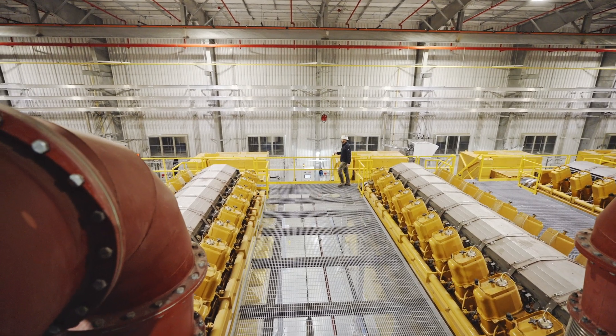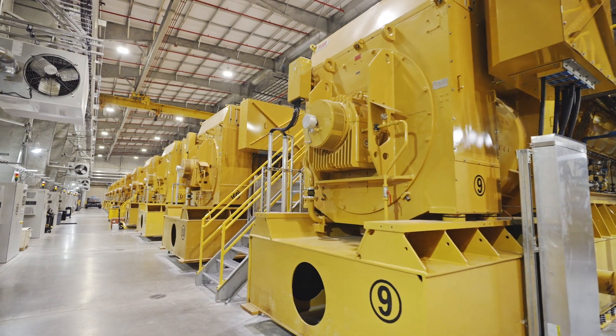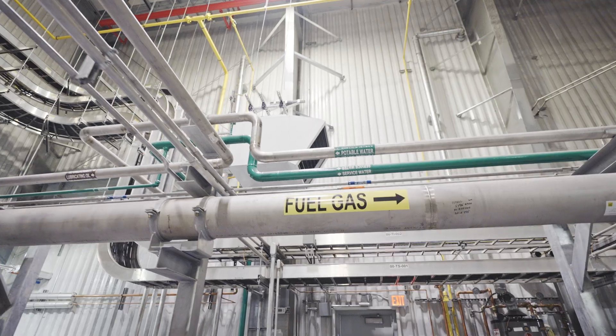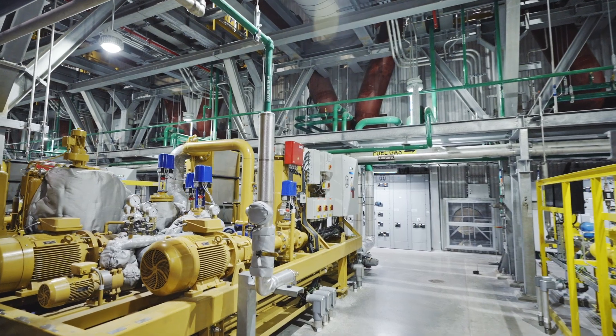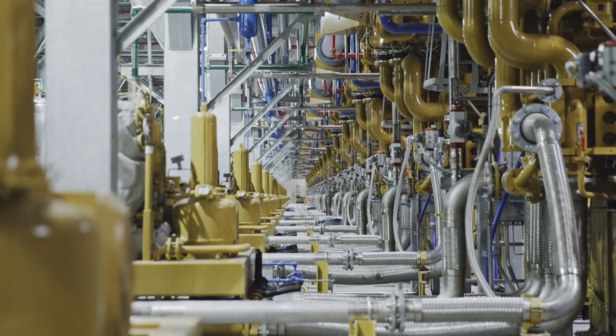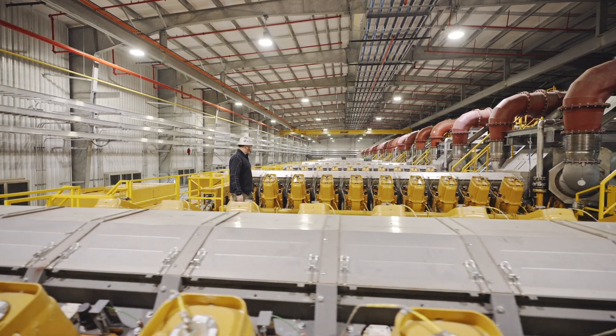This is the engine hall. Inside of this room we have Caterpillar 9.7 megawatt combustion engines. The natural gas reciprocating internal combustion engine, known as RICE units, can ramp up from an idle state in eight minutes, run as long as demand requires, and start and stop multiple times daily.